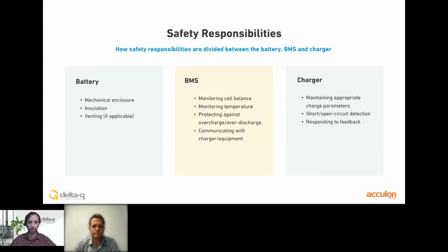Finally, the charger receives those messages from the BMS. If the BMS is sending charge parameters, it will maintain those. Otherwise, the charger might use its own local mode algorithm, responding to the voltage of the batteries to set its current levels, basically maintaining those charge parameters to make sure it's charging correctly.